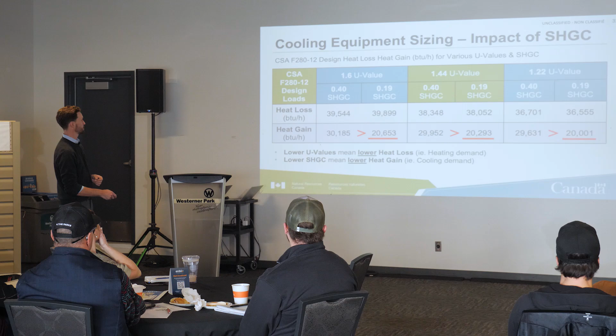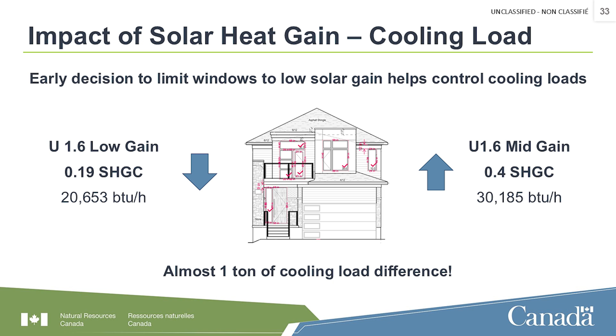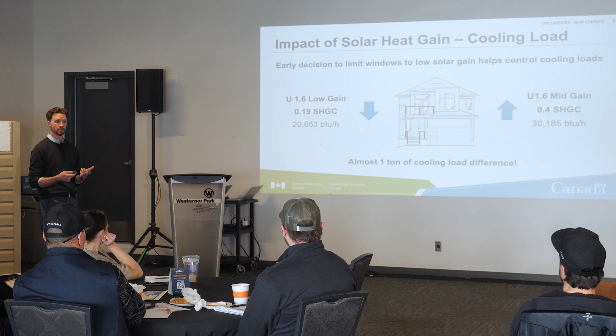So we may start by saying, okay, a U1.6 mid-gain window at 0.4 is achieving my energy goals. But what does that mean? It means that my demand for cooling is at 30,000 BTU. So let's make a decision now to go to a low solar heat gain glass, save a ton of cooling, and achieve a 20,650 BTU an hour cooling load. But what happens here? 1 ton of cooling load difference is great and has a monetary impact on the cost of that equipment. But we've also now moved the energy model and we have to account for that in some other means. What else happens when we do this?